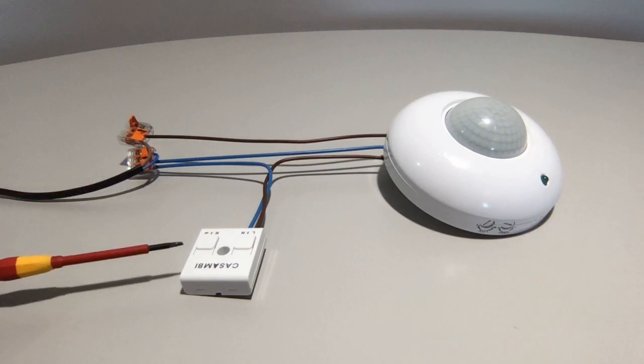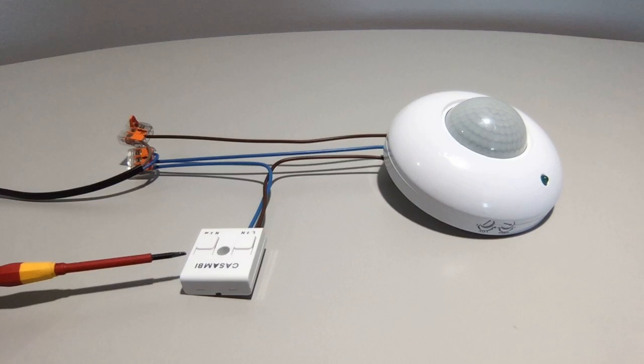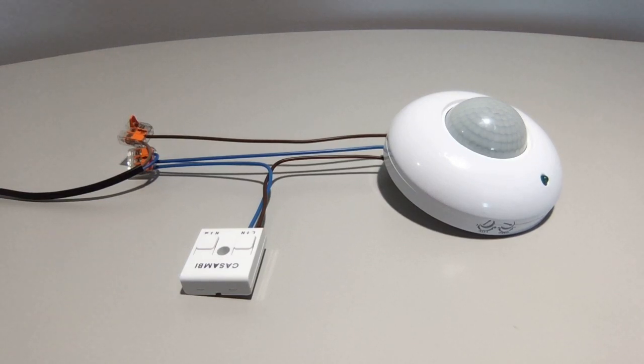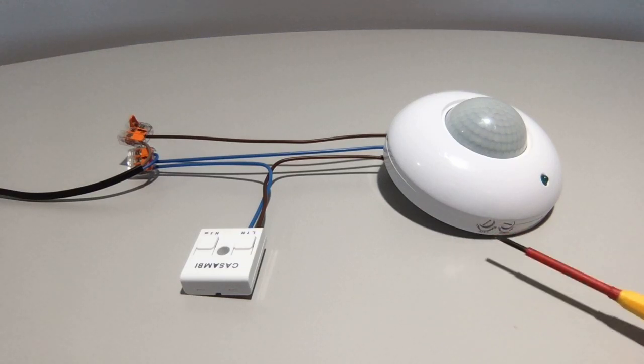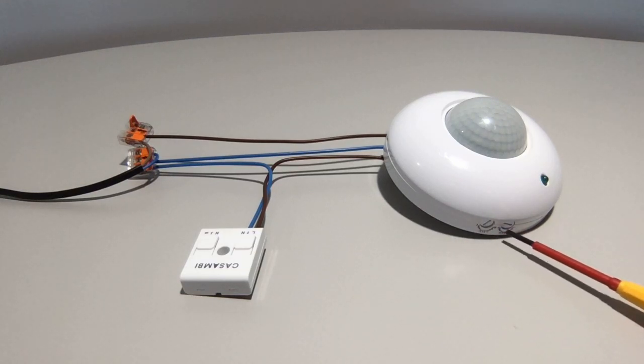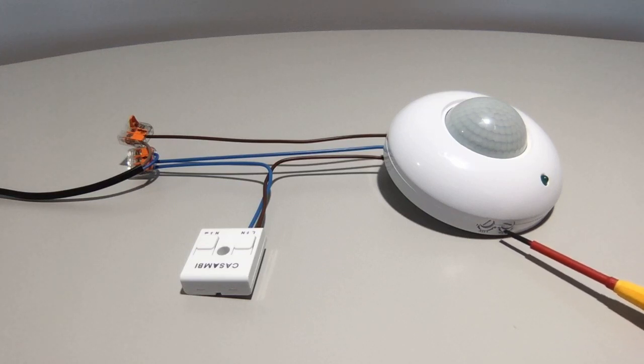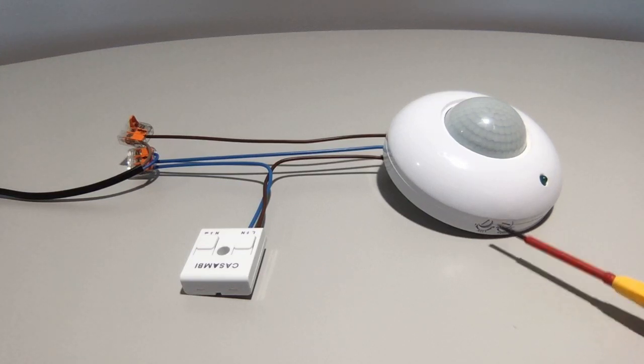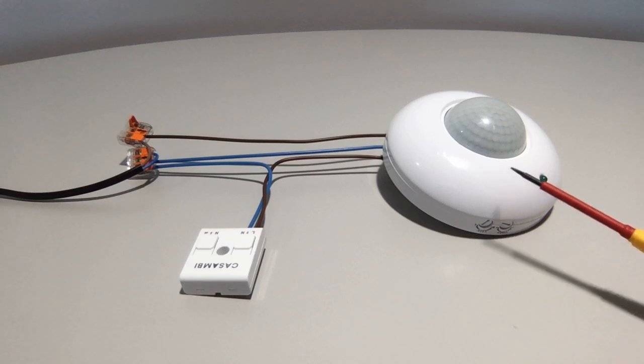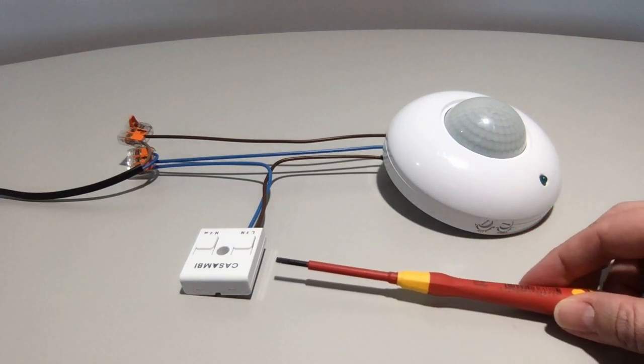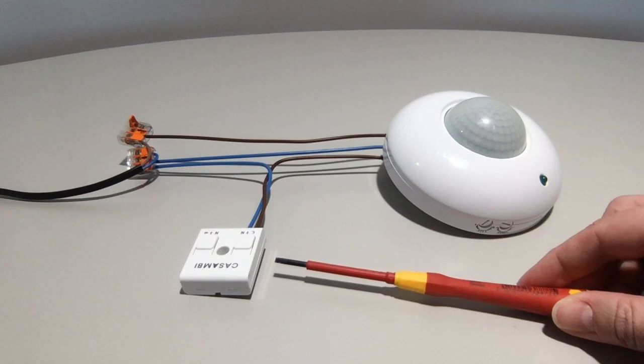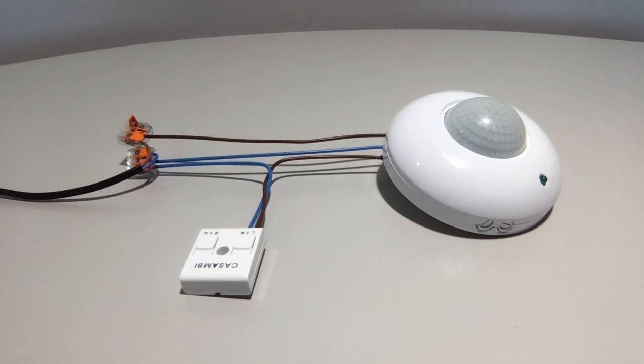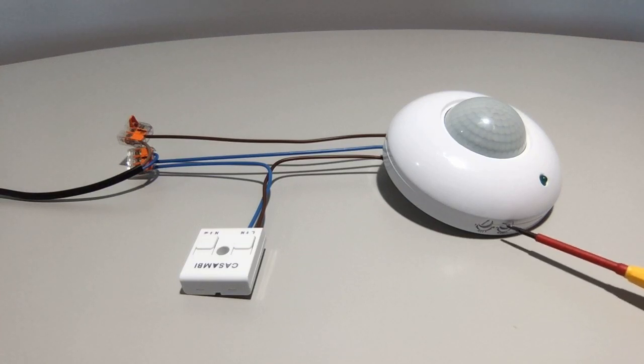I then have my CBUTD which I'll configure as a presence sensor. One important thing to remember that when configuring a sensor like this, it's often best to set the time manually first on the presence sensor, and then possibly set a linger time of maybe one second or five seconds on the actual Casambi configuration. Therefore, you're predominantly altering the linger time using the physical button on the sensor.